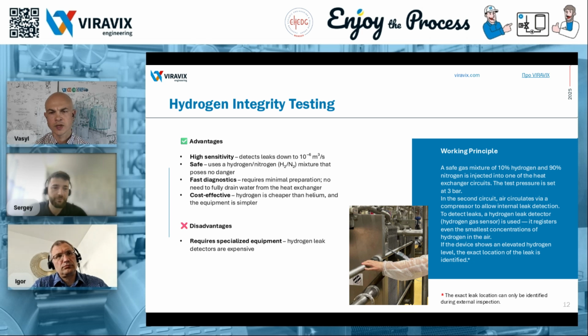Thank you, Sergey. Igor, could you please tell us about the hydrogen method? As I understand it, in this case, we use a gas mixture, right? Since pure hydrogen is flammable, we can't use more than 10% in the test mixture. The critical concentration is around 4%. Above that, the gas becomes potentially explosive. So the question is, how does this method compare in terms of leak detection performance and accuracy when testing heat exchanger integrity?